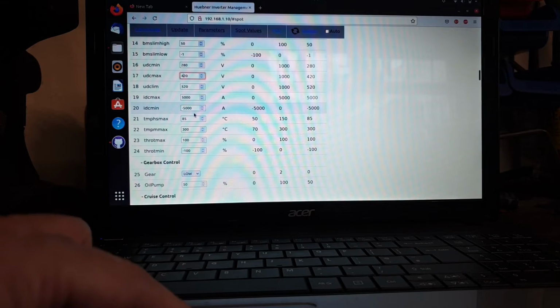TMPHS max is our heatsink maximum temperature. Currently I don't have any cooling on the inverter and the motor here, but that's no big deal since we're just doing little tests. But let's say we had a cooling system failure, or this value was set to a rather stupid value, say 10 degrees centigrade. So if we set TMPHS max to that, let's see what that does for us.